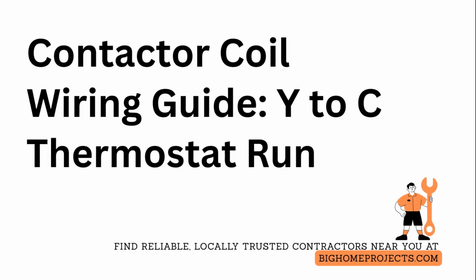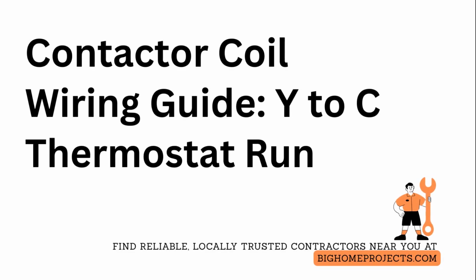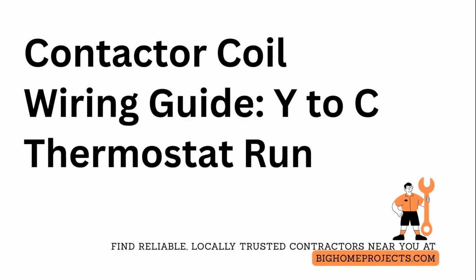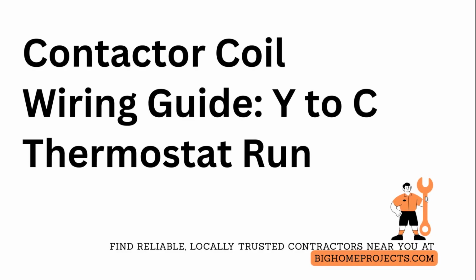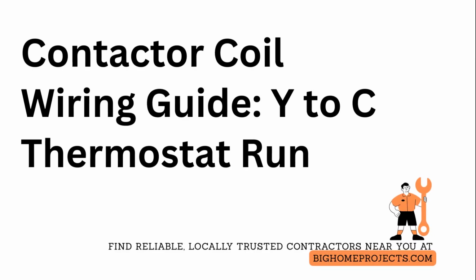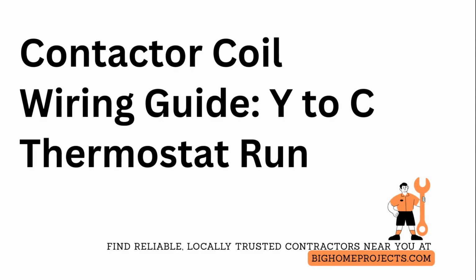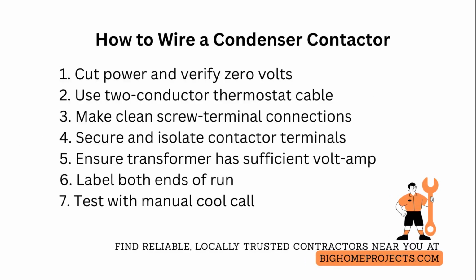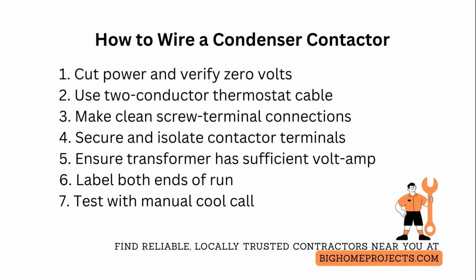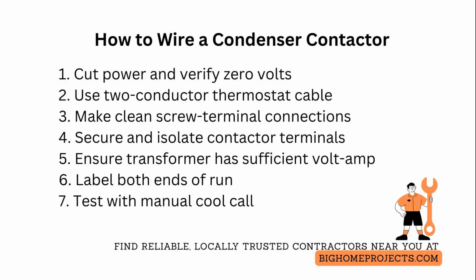Wire the condenser contactor by landing one thermostat call on Y and the other on C at the control board, then run those two wires to the outdoor contactor coil. Polarity does not matter for the 24-volt control circuit. For a reliable, code-safe install, first cut power at both the outdoor disconnect and the indoor service switch and verify 0 volts with a meter.